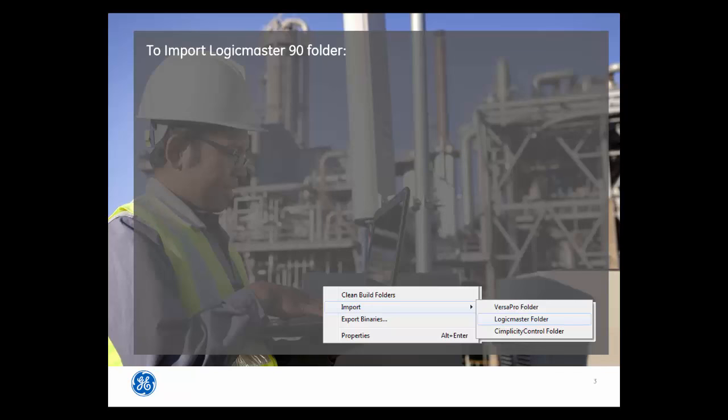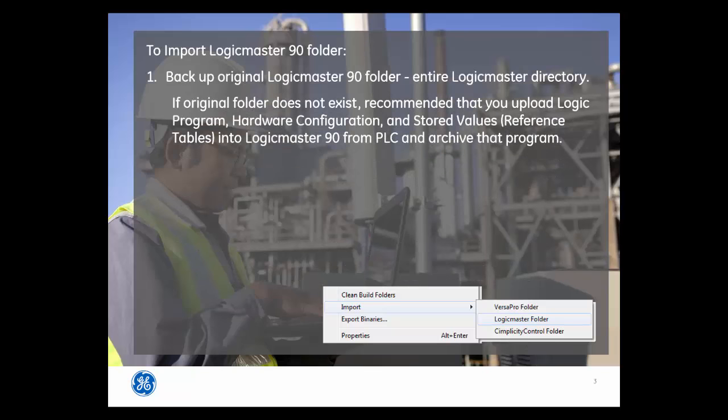To import a Logic Master 90 folder, follow these steps. First, back up the original Logic Master 90 folder — for example, zip up the entire Logic Master directory. If the original folder does not exist, we recommend that you upload the logic program, hardware configuration, and stored values, or reference tables, into Logic Master 90 from the PLC and archive that program.